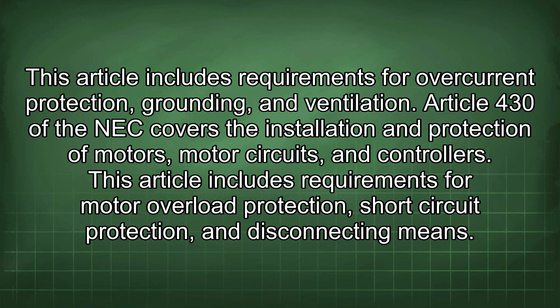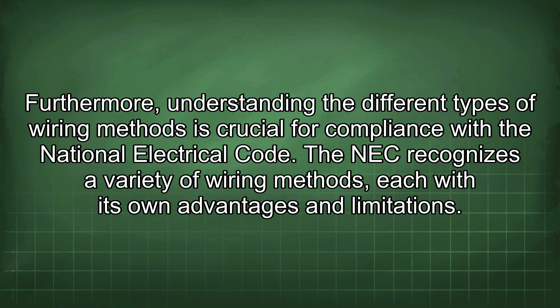Furthermore, understanding the different types of wiring methods is crucial for compliance with the National Electrical Code. The NEC recognizes a variety of wiring methods, each with its own advantages and limitations. Some common examples include rigid metal conduit, intermediate metal conduit, electrical metallic tubing, flexible metal conduit, armored cable, non-metallic sheathed cable, and underground feeder and branch circuit cable.